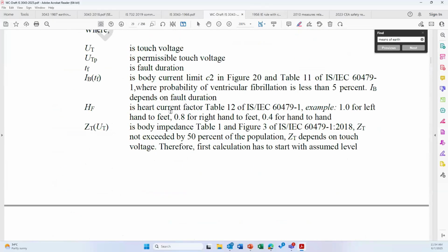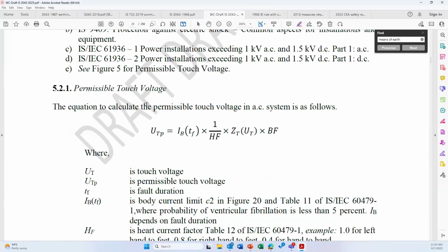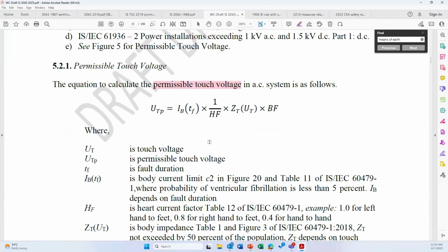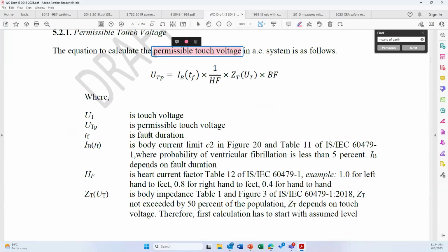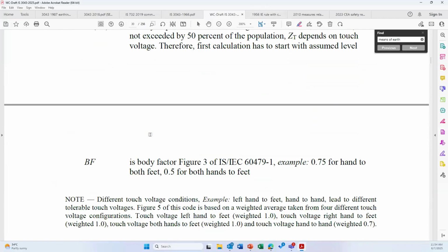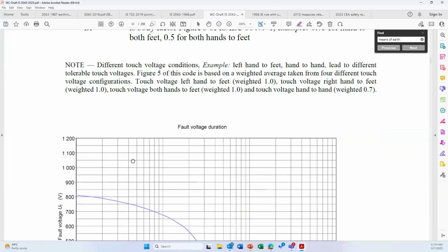Example, the calculation of permissible touch voltage. Please note that in the new standard, there will be a lot of new terms, permissible touch voltage, prospective permissible touch voltage, and so on. So this is the method to calculate the permissible touch voltage, and you can also see the information in IEC 60479 as well as IS 732.